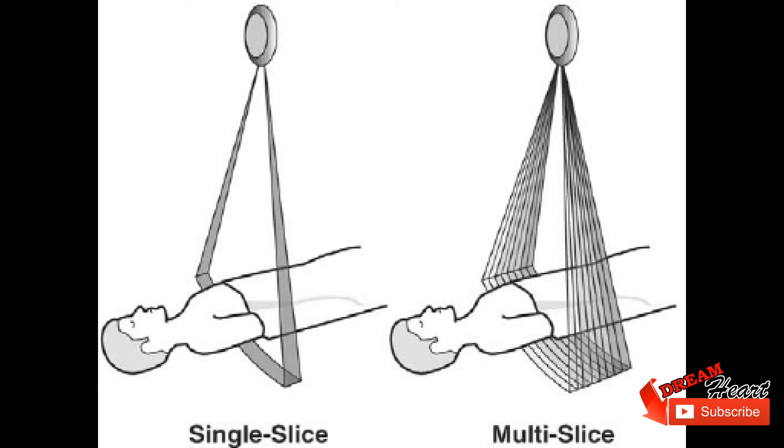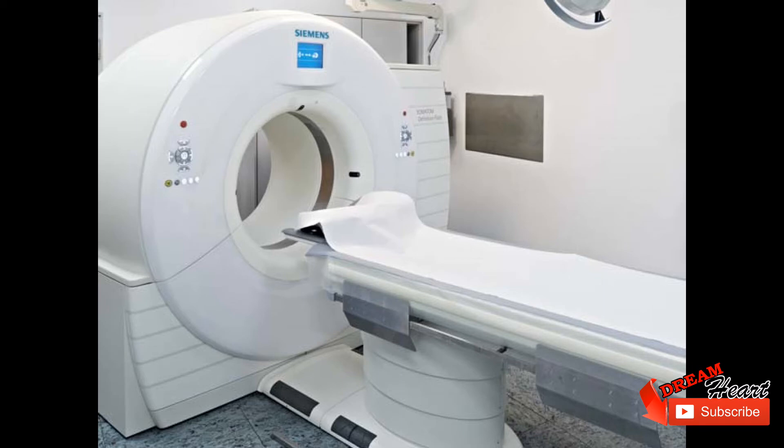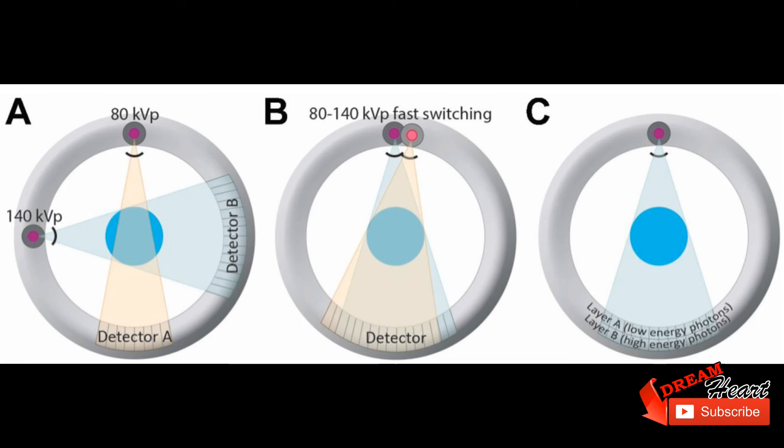Current models from 2007 have up to three rotations per second and isotropic resolution of 0.35 millimeter voxels with z-axis scan speed of up to 18 centimeters per second. This resolution exceeds that of high resolution CT techniques with single slice scanners, yet it is impractical to scan adjacent or overlapping slices. However, image noise and radiation exposure significantly limit the use of such resolutions.